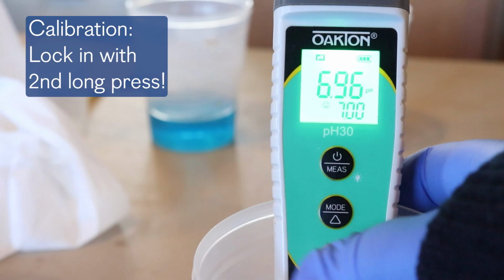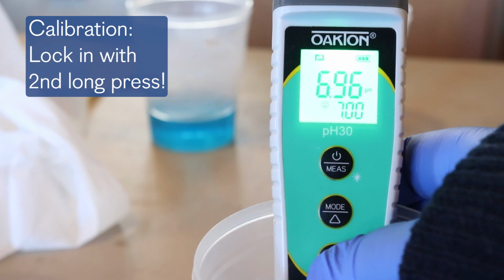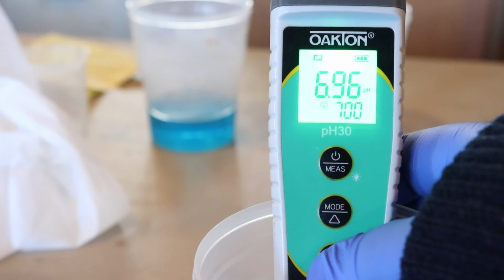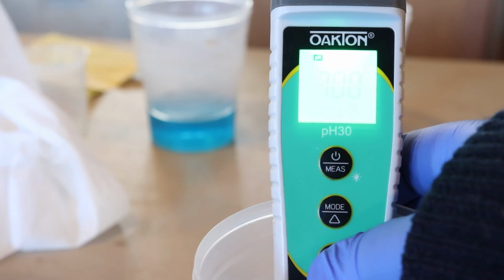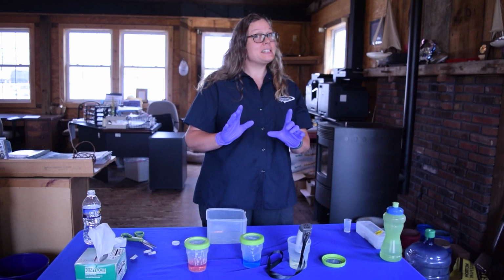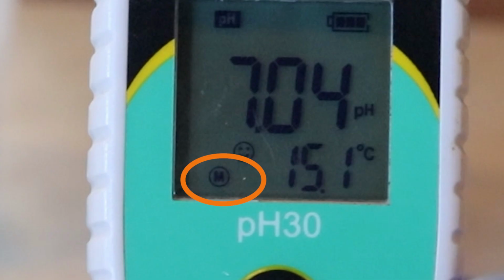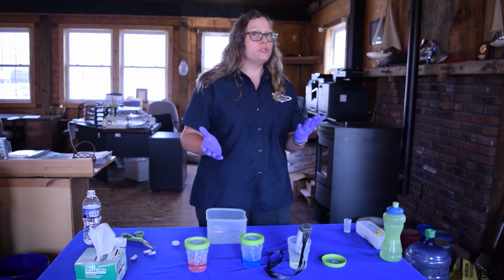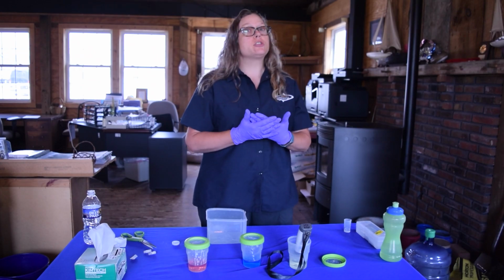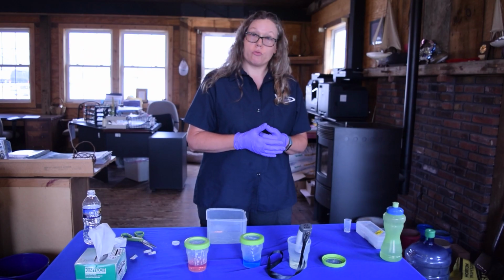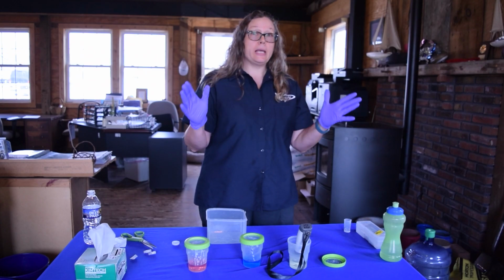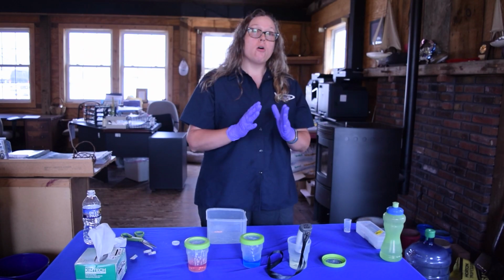To lock in your pH calibration, you're going to do another long press on the cal button, and that will return you to your main screen. At that time, look at your screen. Make sure that you see a circle with an M on the screen. If you do not, that means that your calibration did not go through. There should only be, at this point, the M on the screen.